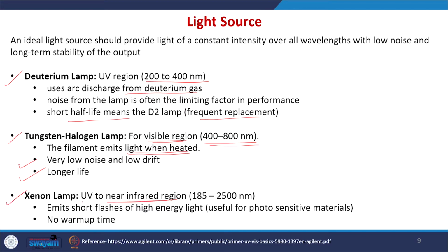So, it can measure your sample from UV to near IR region, that is from 185 to 2500 nanometer. It emits short flashes of high energy light, and it is mainly useful for photosensitive materials, and here there is no need for warm up time of the lamp.